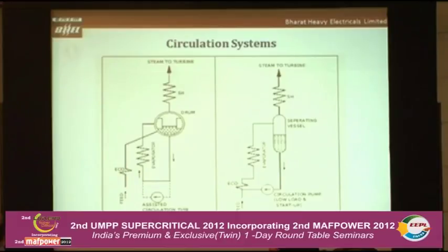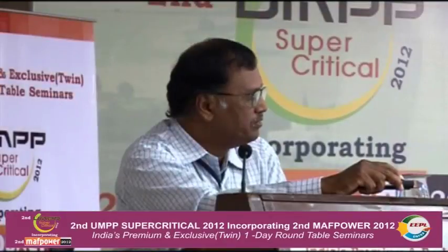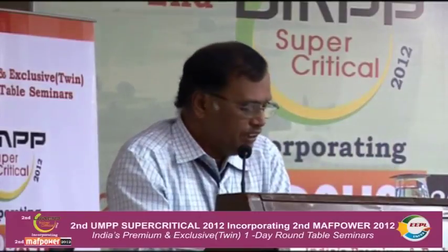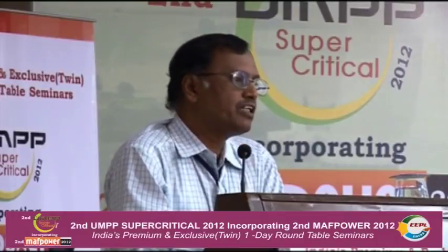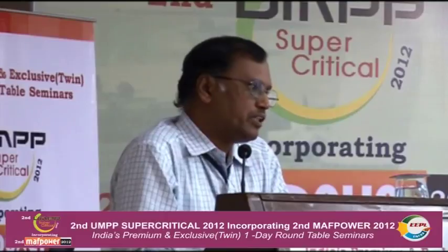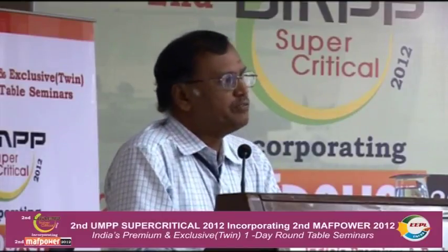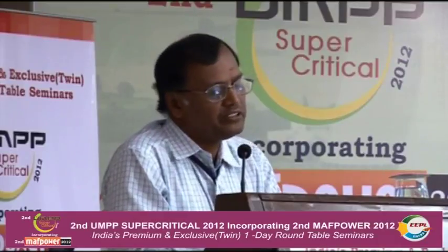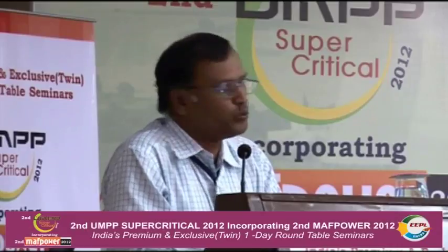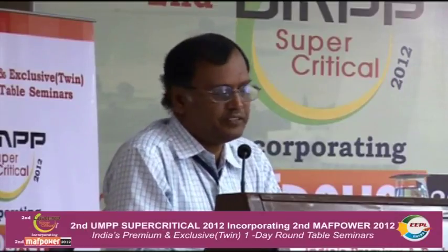And this is a small circulating pump. This is used to circulate, say, up to 35% flow, because in that low load operation, the flow through the water wall is very low. Therefore, the heat flux felt on the water wall is so heavy that it is likely to damage it. Even though we are not using carbon steel but alloy steel, still it is not possible. Therefore, we have to maintain a certain amount of recirculation. That is called the minimum once through load. It varies from 30 to 40% BMCR. Generally, it is 30% BMCR.